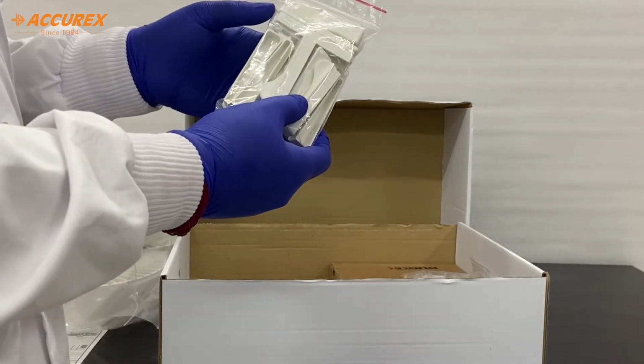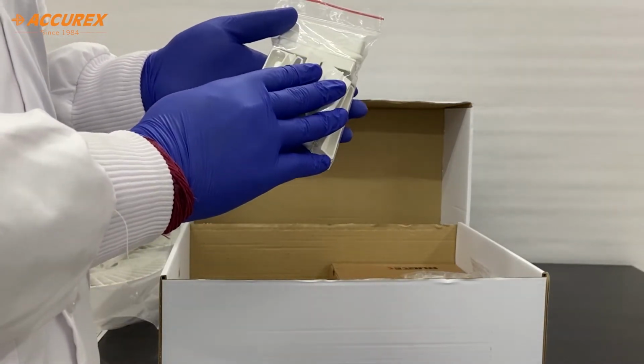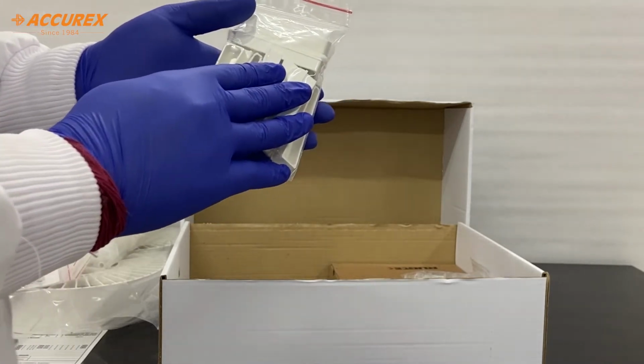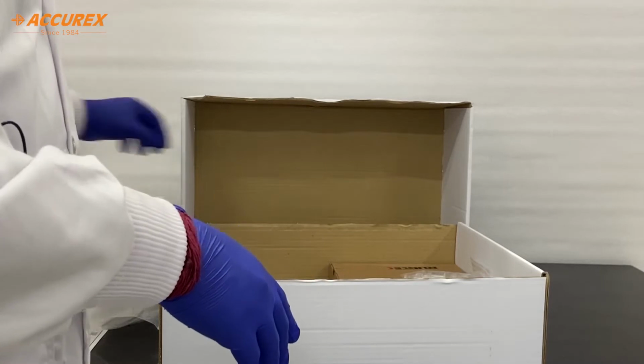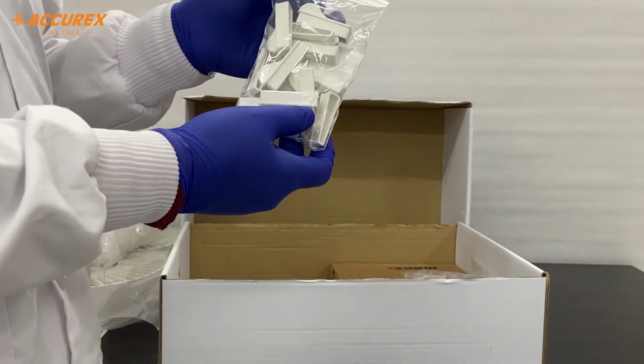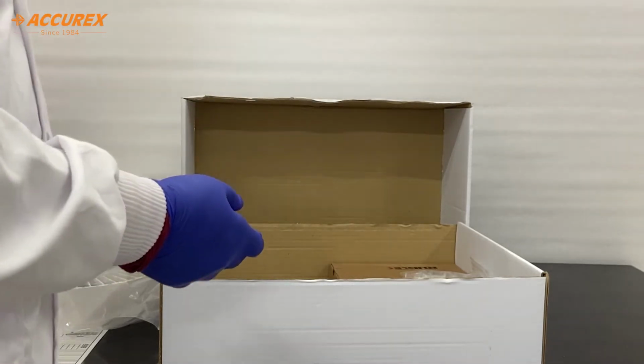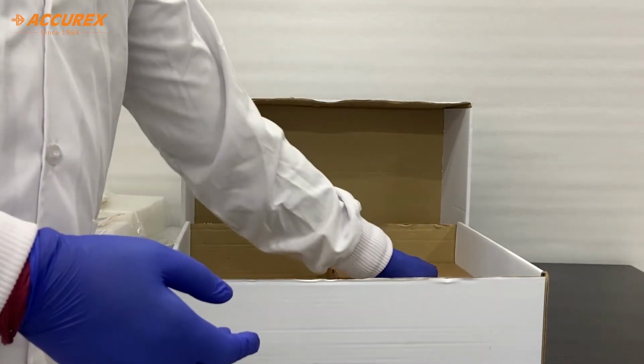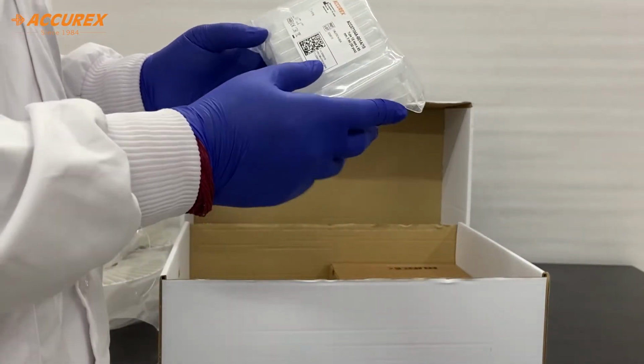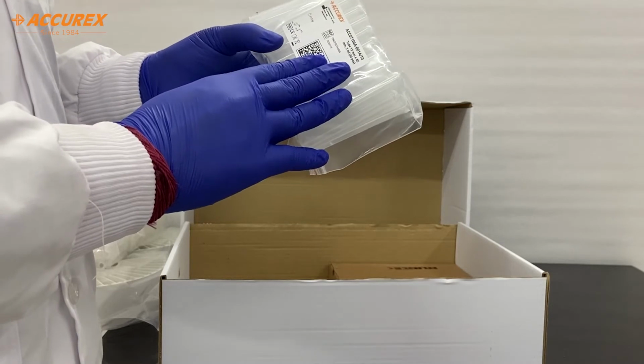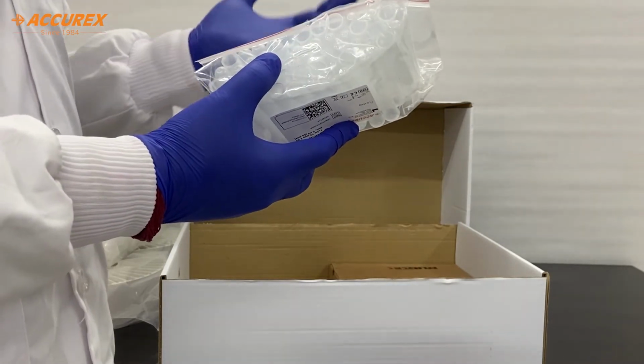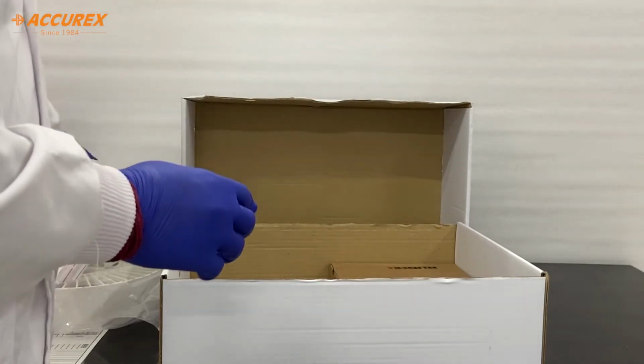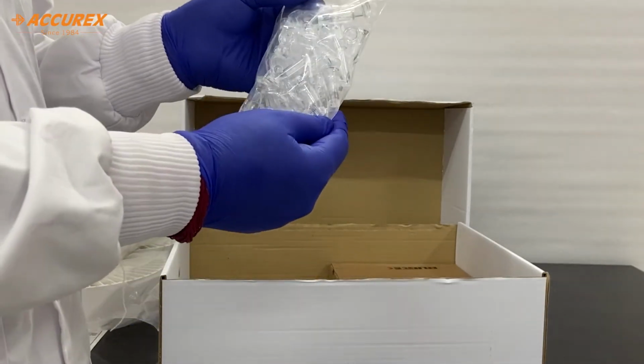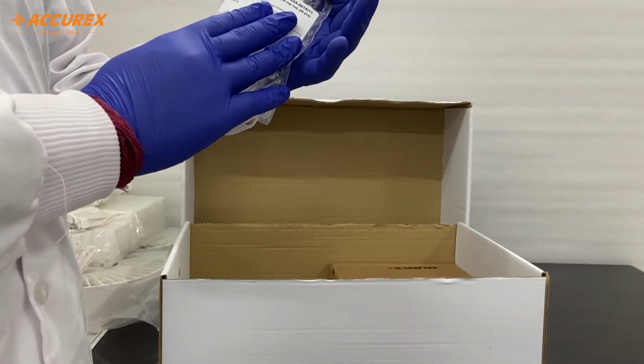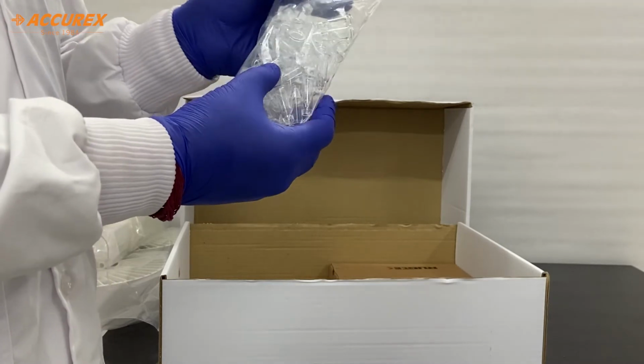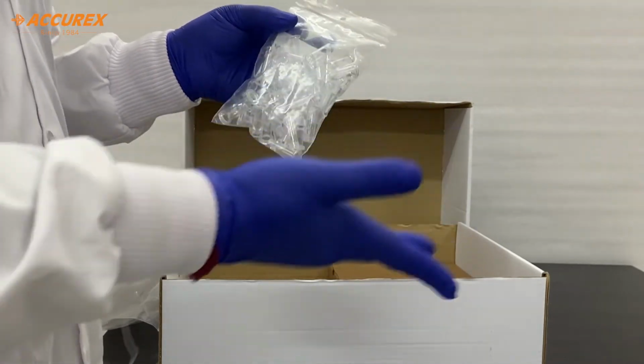Then we have bottle lids. When no reagent is used, you can close the bottle with this lid while placing the bottle. This lid is used for the 20 ml bottle. Then, moving on to the tube part, we have tubes of 12 mm, 50 pieces. Again, this is used when you want to run the sample or reagent in tube mode. Then we have sample cups. Again, we provide 50 pieces with the installation kit. It is a 1 ml cup. We can use it for sample or reagent purposes also.